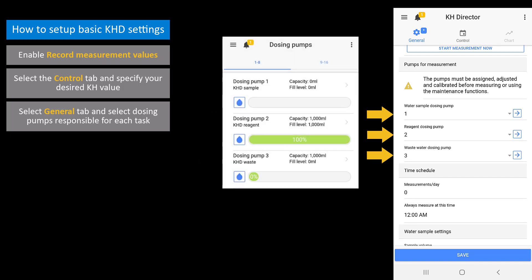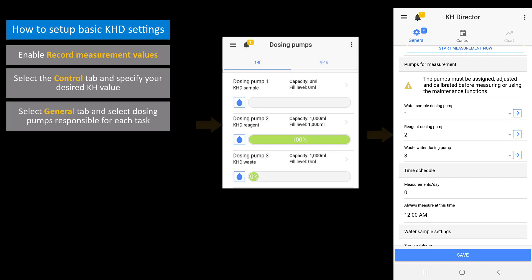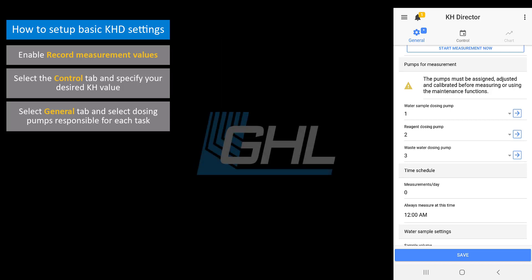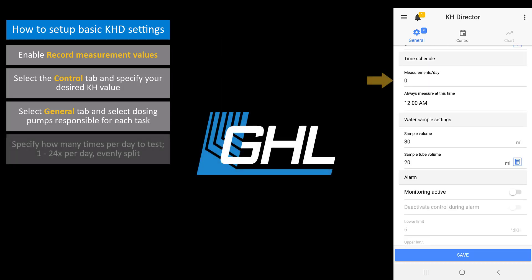For example, in part 2 of the video we chose pump 1 for the water sample, pump 2 for the reagent, and pump 3 for the wastewater. In the Time Schedule section, specify how many times per day you want to do a KH test. You can have the KHD automatically test anywhere between 1 to 24 times per day. If you choose to test more than once per day, the testing intervals will be evenly split throughout the day.